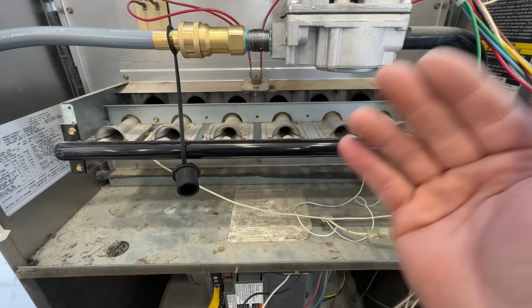So let's turn the blower motor on and do this same test to see the results. If you have some jumper wires and you're using this method, you can simply jump R and G, and that will signal just the fan to come on so you can do this test. Let's go ahead and throw this screw back in.